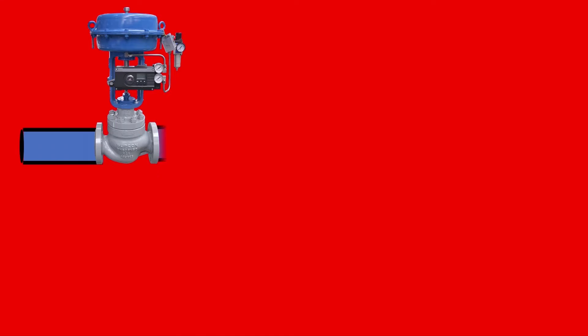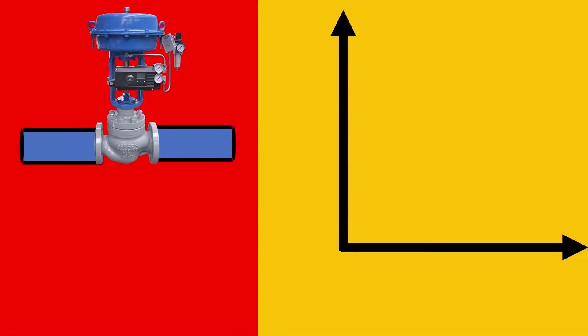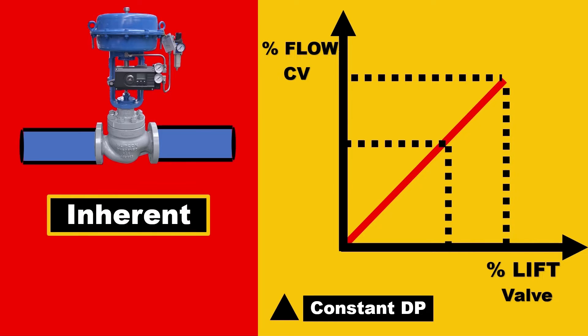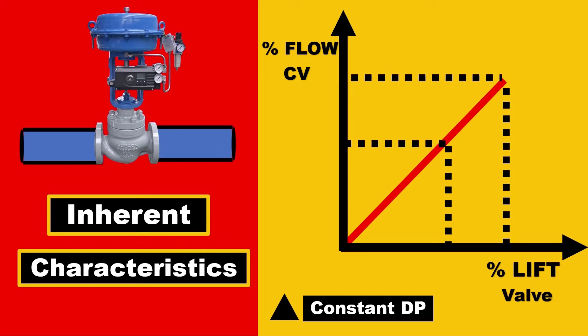When you have valves in a testing line and plot a curve with the x-axis showing percentage lift and the y-axis showing flow in CV, with constant DP, you get a very linear curve. At 100% valve lift, you get 100% flow. At 50% valve lift, you get 50% flow. These are called inherent characteristics of the valve.